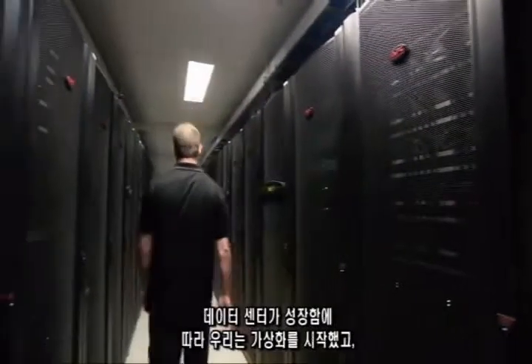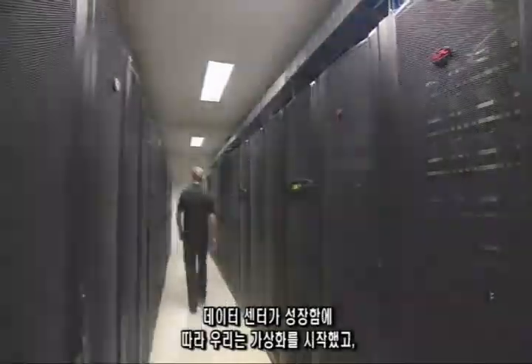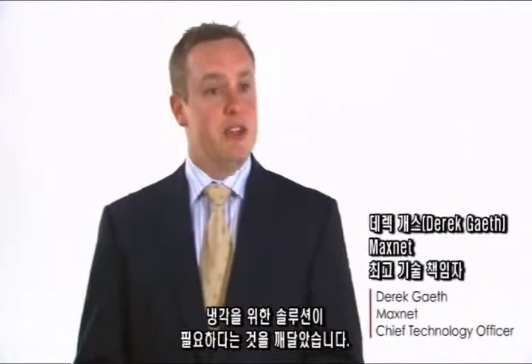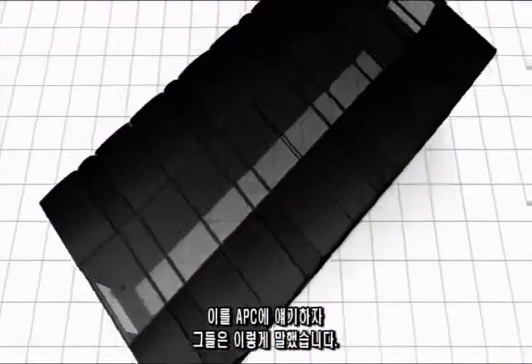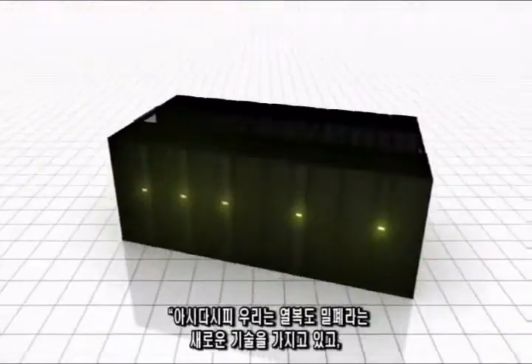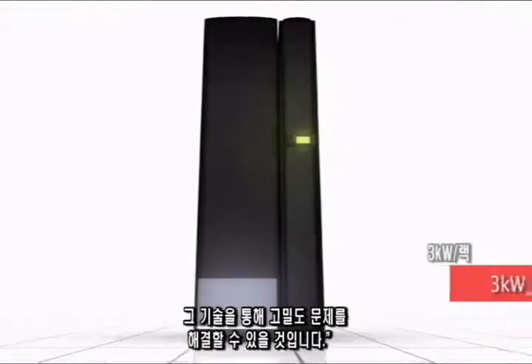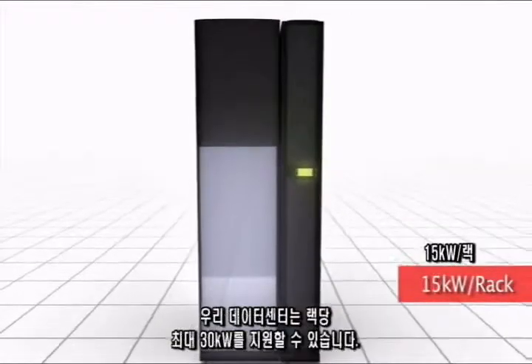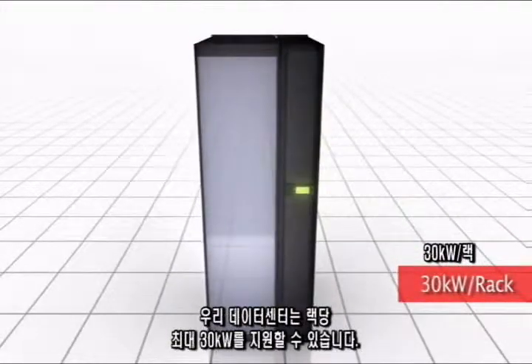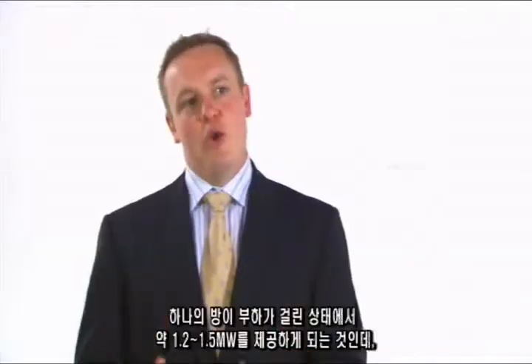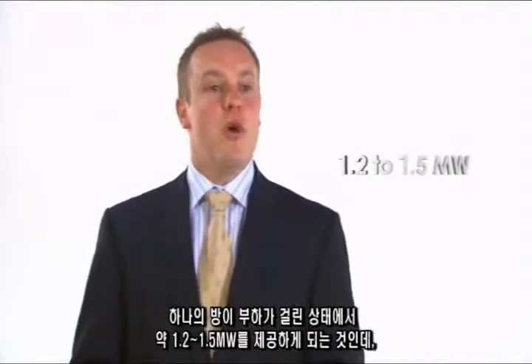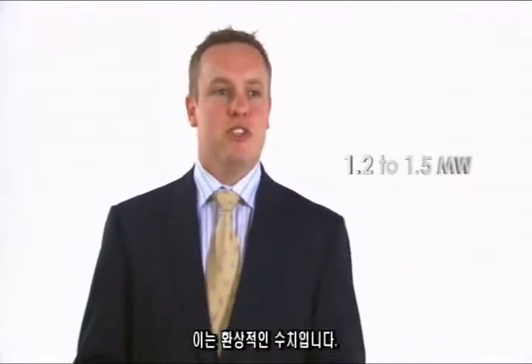As our data centre began to grow and we started to virtualise, we realised that we needed a better solution for cooling. We talked to APC and they said, hey look, we've got this new technology coming out in the market called hot aisle containment, and that will allow you to do high density. So we are able to support in our data centre up to 30 kilowatts a rack, and that's pretty amazing. Our room will be running at about 1.2 to 1.5 megawatts worth of load, which is just fantastic.